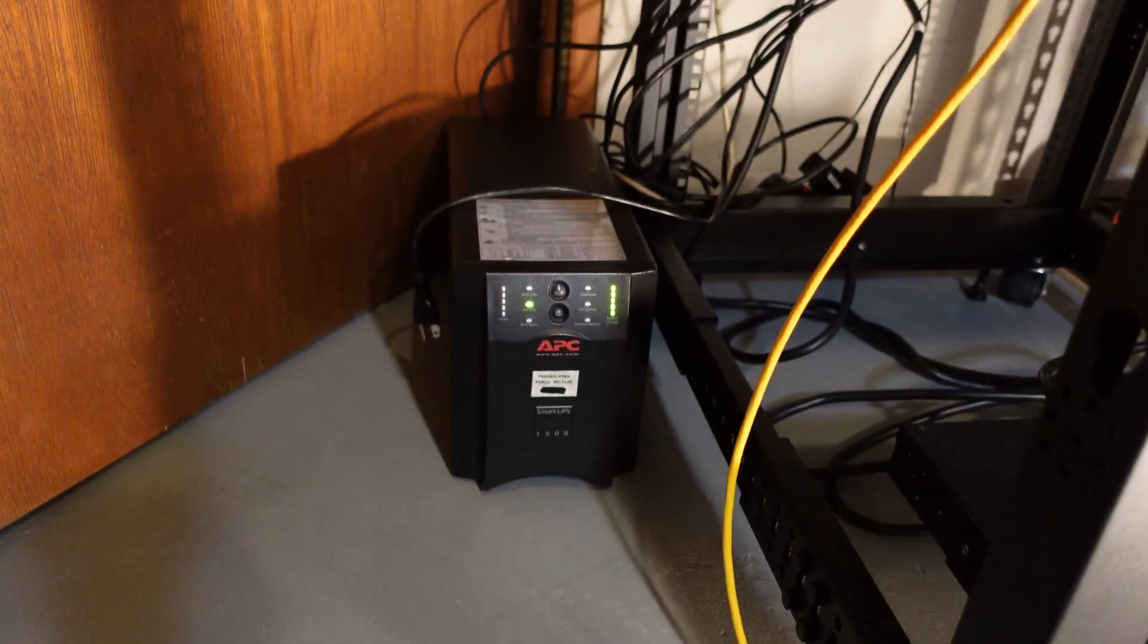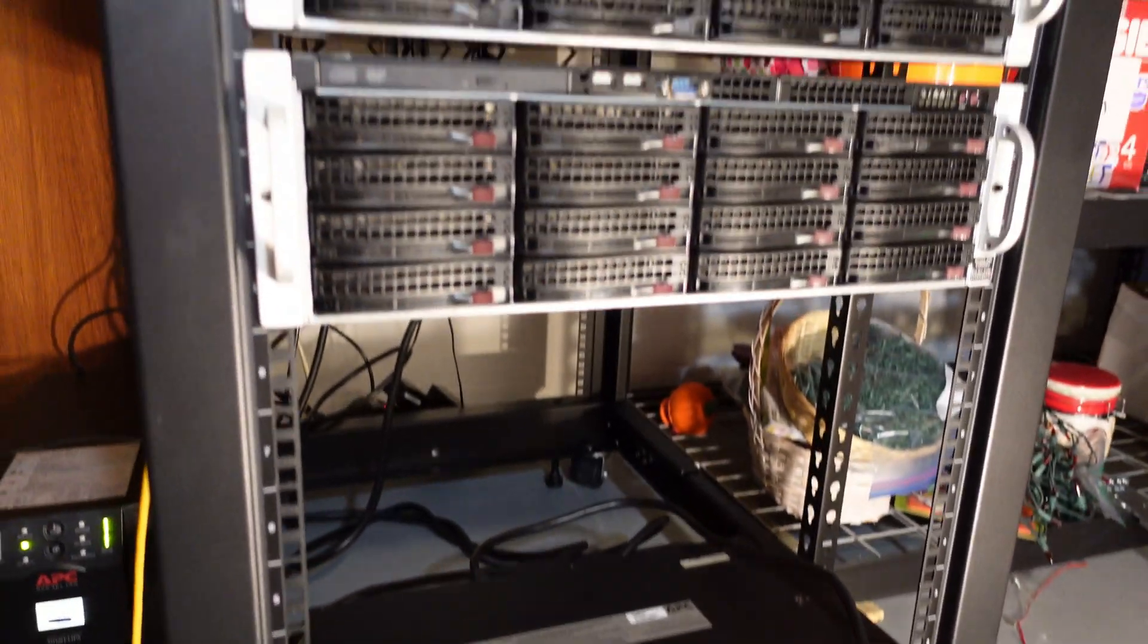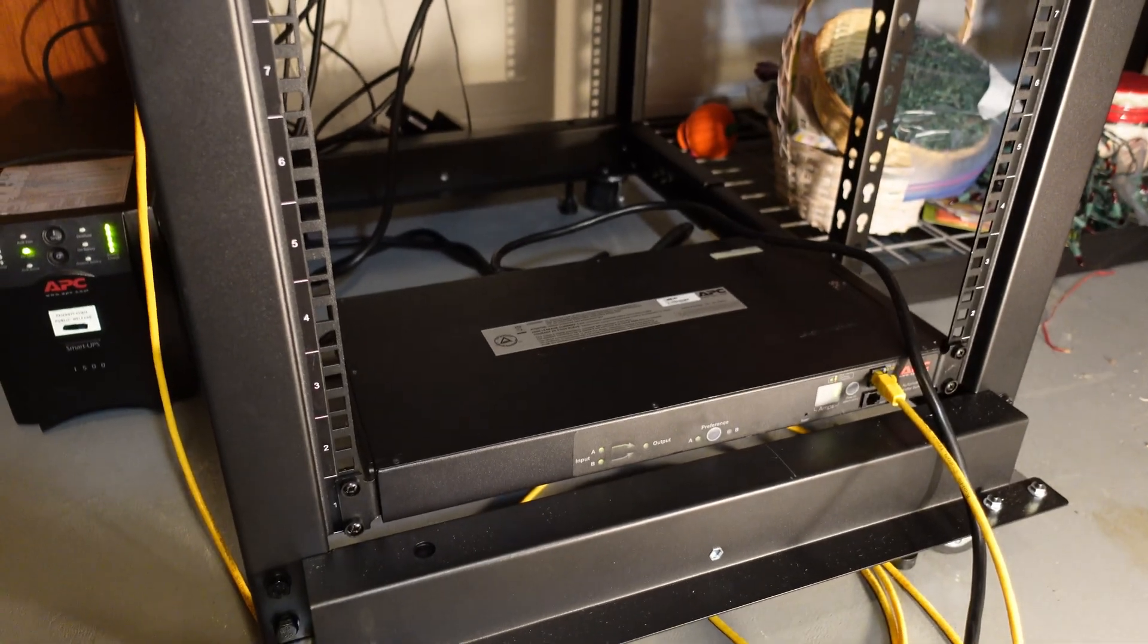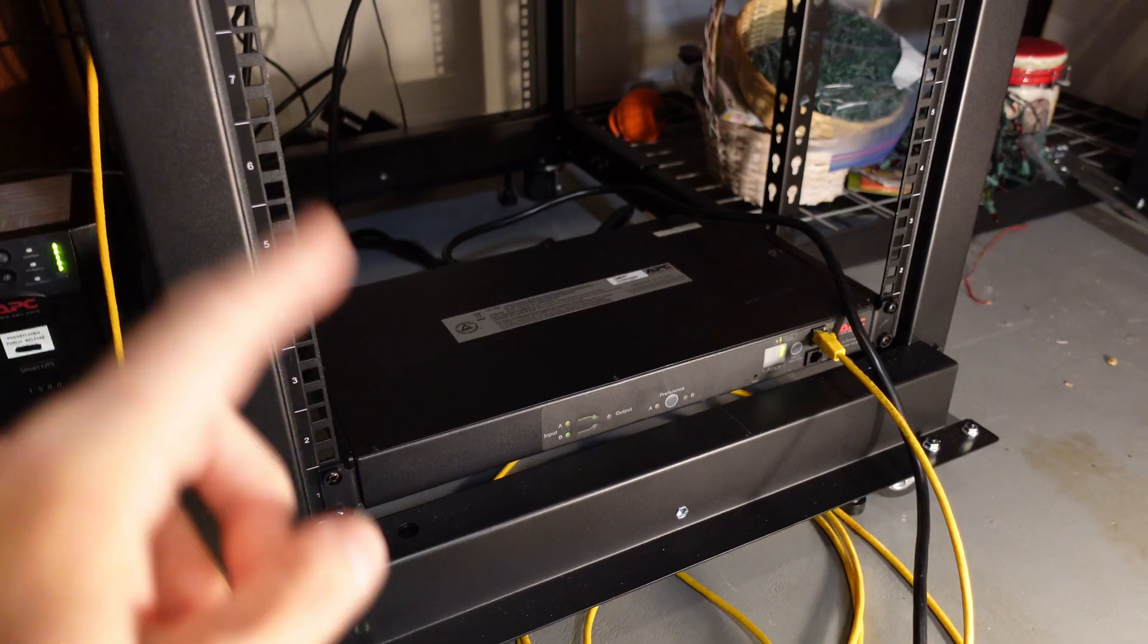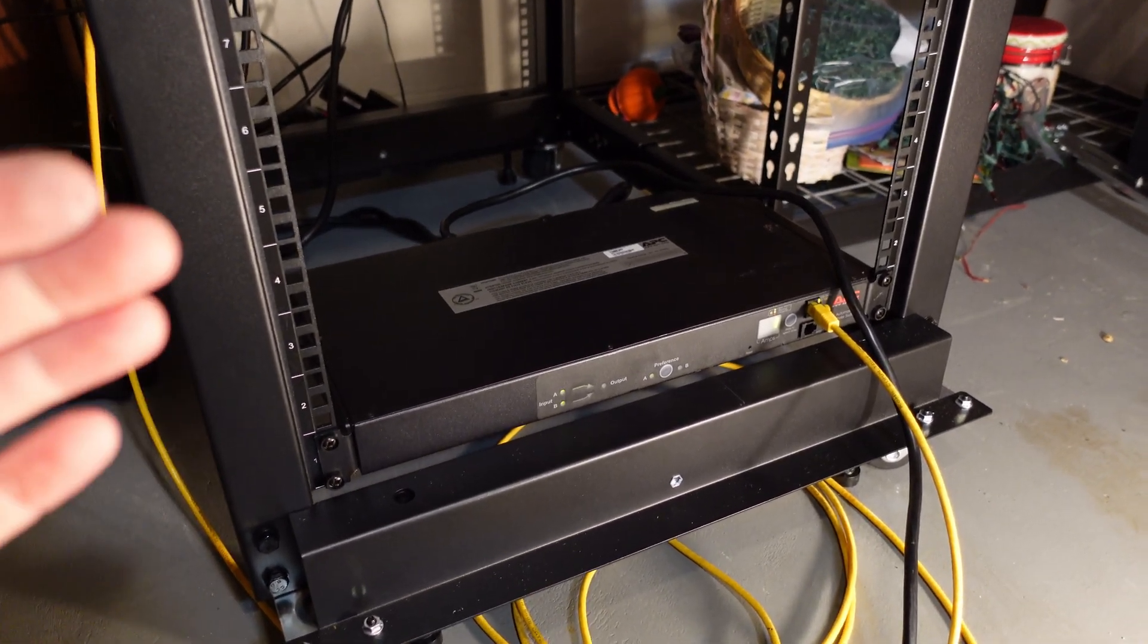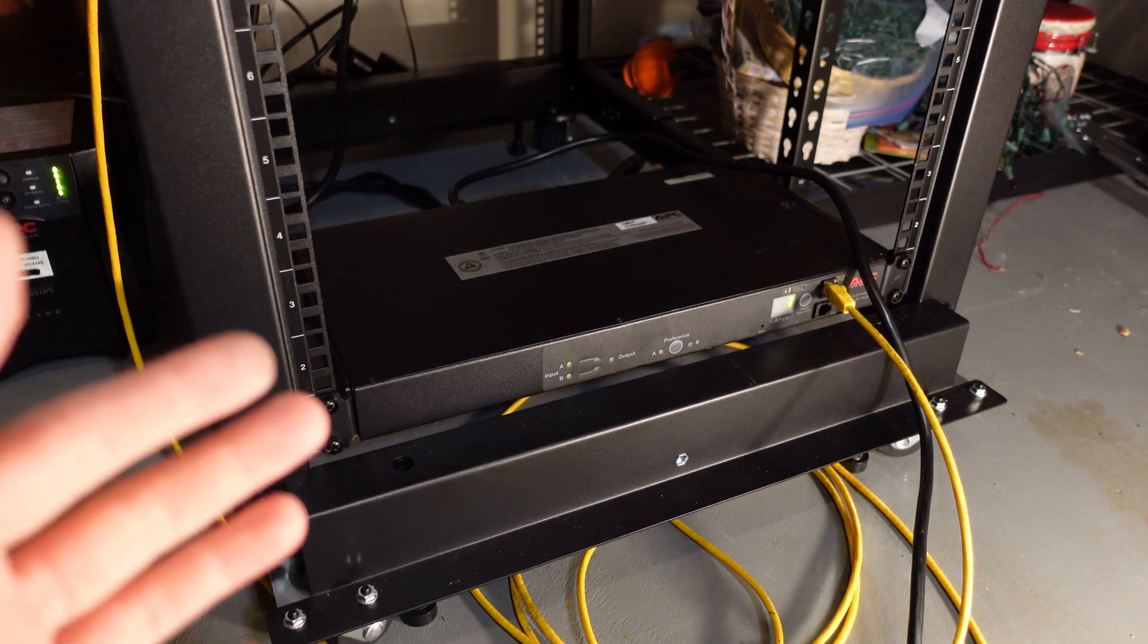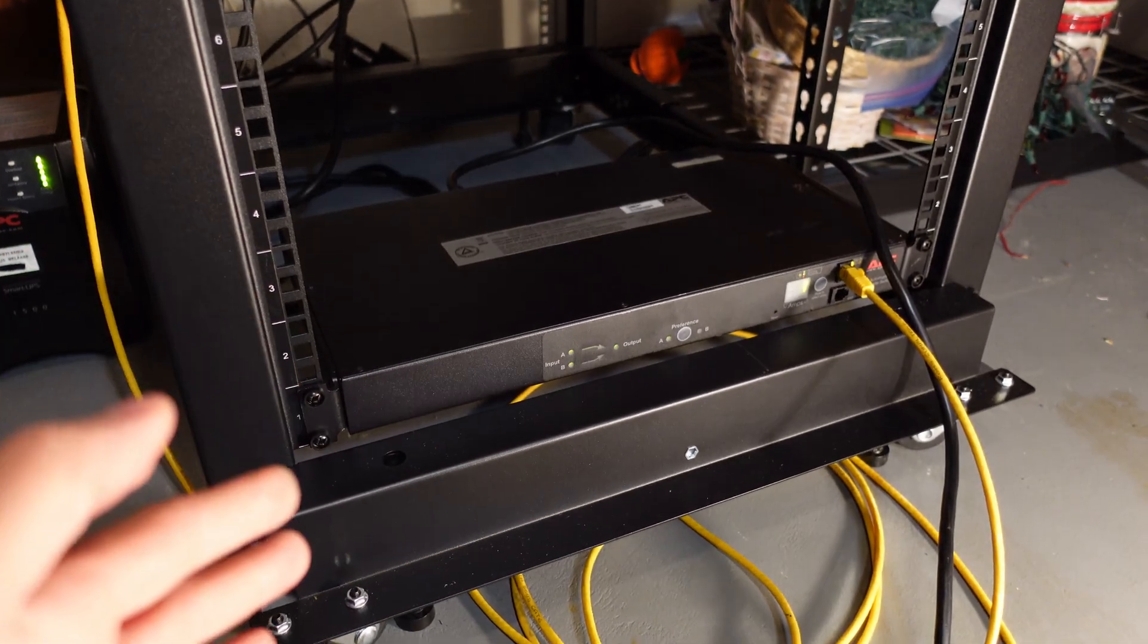All right, so I pulled out the old UPS and set it on the side there. You can see I've got the new transfer switch here racked in the bottom of the rack. Everything in the rack is shut down except for the networking equipment there at the top. And before I move some plugs around, I just wanted to test how this works. You can see I've got some incandescent light bulbs over here, so I'm just going to unplug each source and verify that it transfers correctly. I believe it's now working. I did have a little bit of drama getting it to work - I don't know if it was a firmware issue. I did update the firmware or some of the components. I don't know what the deal was, it wasn't transferring the first time, but I think I have it working now. So let's just double check before we plug in our components.